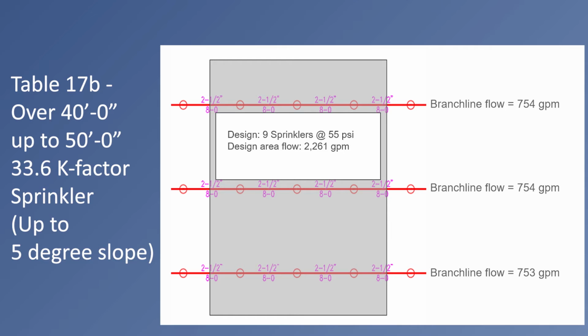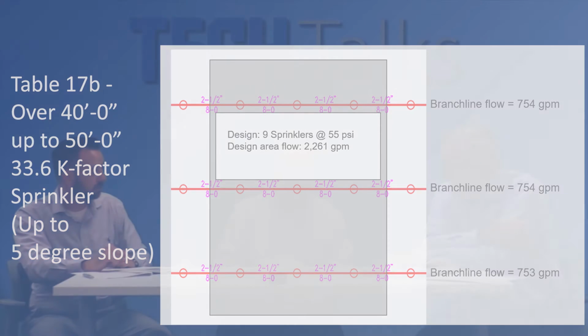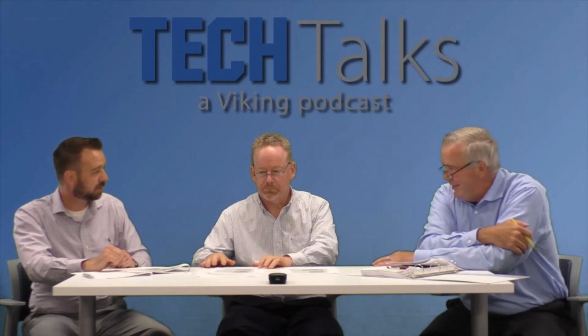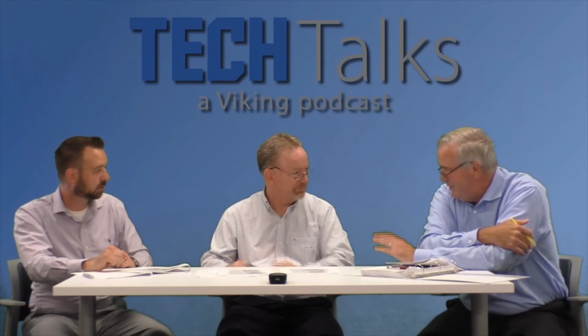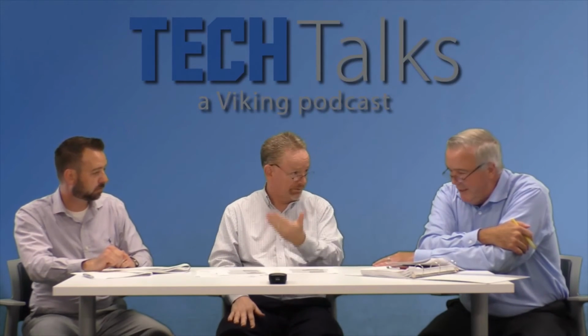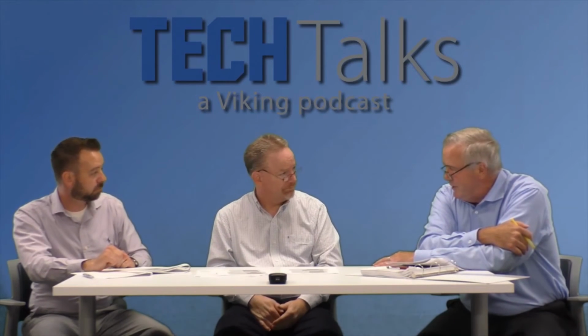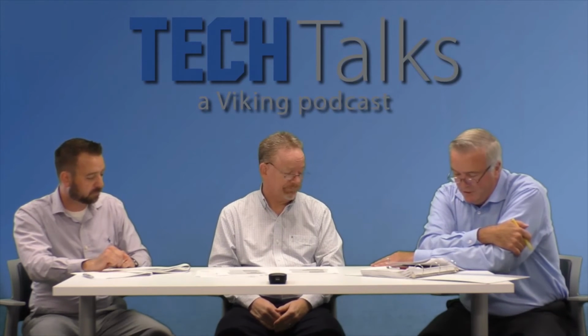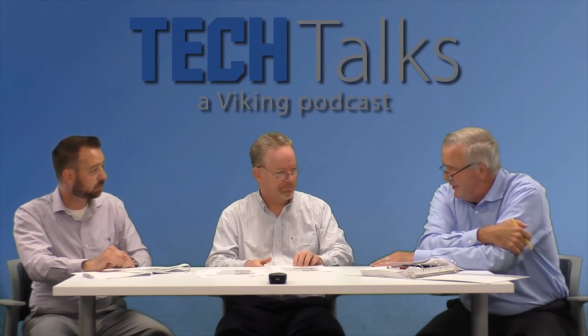600 gallons more, correct, and 15 PSI on the start pressure, that's pretty significant. I know a lot of people will go crazy over this. This is sort of a default listing from the 55-foot application that the manufacturer of the K33 has. This was not their target for 50-foot ceilings, but it's there. It is on the table with a 9 sprinkler design. But this would be a real tough one to use for that ceiling height.